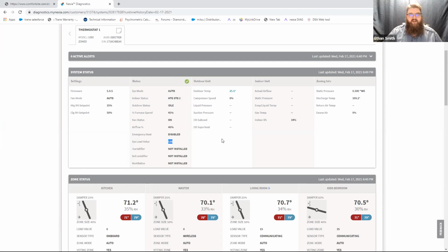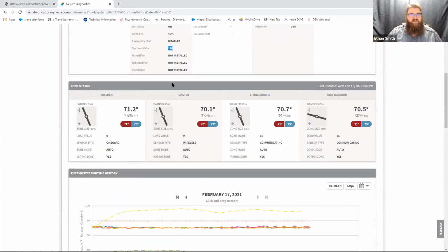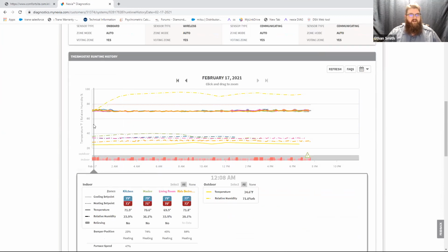You can see his total system load value. So he's above 100 on his load value, so he is calling for stage 2. And you can see all of his damper positions. So right now, load value primarily is in the kid's bedroom. And that zone size is 30%. So he does have some excess air that he's got to deal with. So the strategy that they're using to deal with his excess air is to actually crack those dampers open 25% to that minimum position to bleed some of the excess air off that he's got in this zone. That damper looks like it's in motion right now. Okay, we can also come down here and we can see all of his zones. As we cursor across, you can see down in the bottom left-hand corner of my screen that you've got all the current status of the zone. So let's zoom in here a little bit.